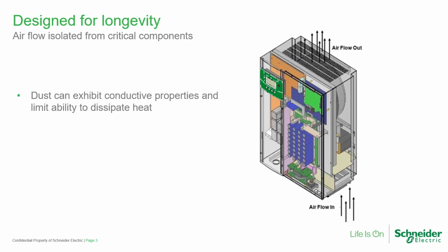XW Pro isn't simply improving an outdated concept. It's a proven design with up-to-date functions and features. Part of the reason we have literally thousands of XW legacy models as well as Plus models in the field as we speak is because it is designed for longevity. Dust can possess conductive properties, and an accumulation of dust on electronic components can limit their ability to dissipate heat. Dust can also accumulate on fan blades, reducing airflow CFM. It should be noted the XW Pro does not draw air across the electronic components, but it draws air through a completely isolated compartment.